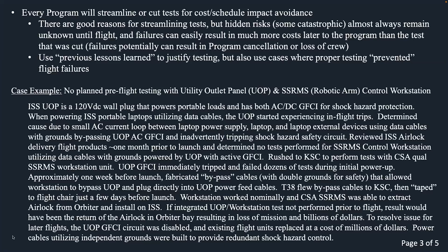The UOP started experiencing in-flight power trip-offs when we plugged in laptops that used data cables. What was happening was that small, non-hazardous AC stray currents from the power supplies were bypassing the UOP AC GFCI and inadvertently tripping the shock hazard safety circuit. This was investigated and corrected by starting to use cables with double-insulated grounds and other modifications.